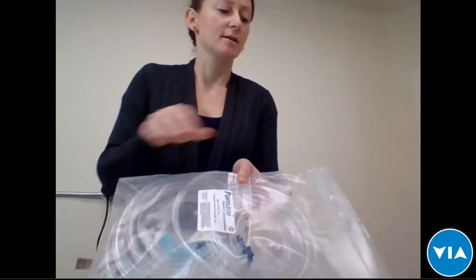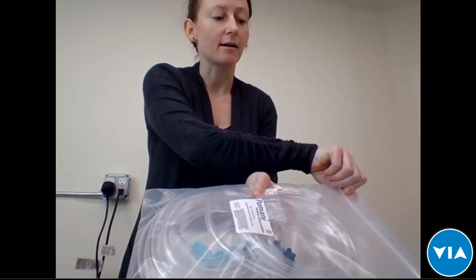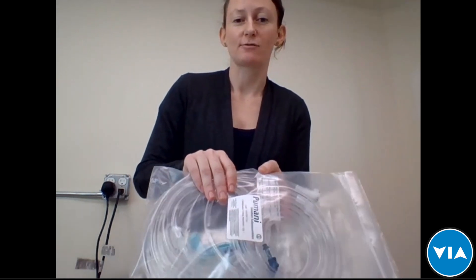The Pumani has a CE marking and is manufactured in an ISO 13485 certified facility. Regarding warranty, the actual Pumani unit has a two-year warranty. Accessories have a lifetime warranty until the package is opened, so it's important to visually inspect accessories when you receive them and report any problem right away. For distributors who purchase in bulk to sell later, the lifetime warranty on accessories until they're opened is particularly useful.